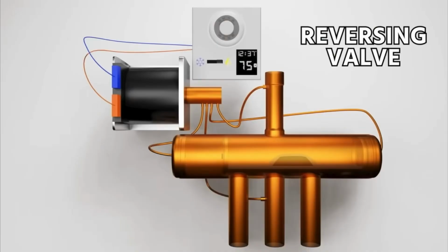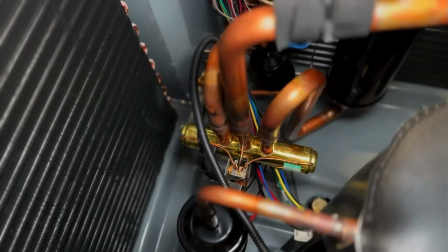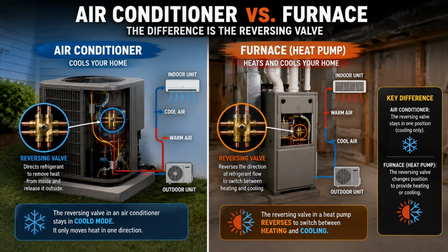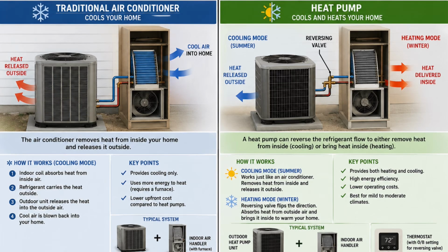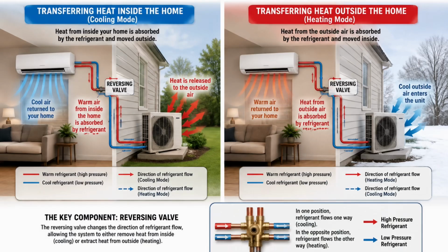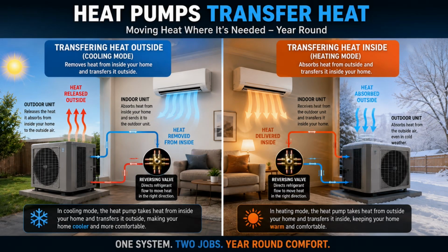So this little device right here is the reversing valve, and that little device is the only difference between an air conditioner and a heat pump, with the exception of a defrost control board and a few other control logic and wiring items, but mechanically speaking, this is the major difference. And what this component does is it reverses the flow of refrigerant so that instead of transferring heat from inside the home to outside, it transfers heat from outside the home to inside the home. And in a nutshell, that is what defines a heat pump and makes it different from a traditional air conditioner.